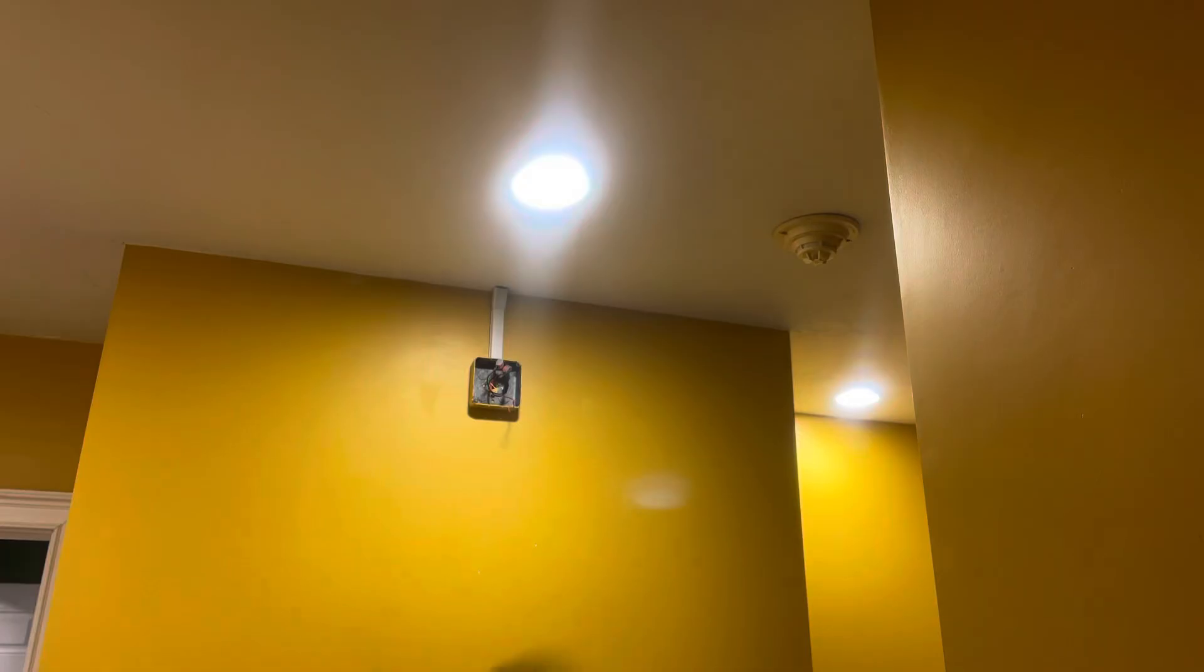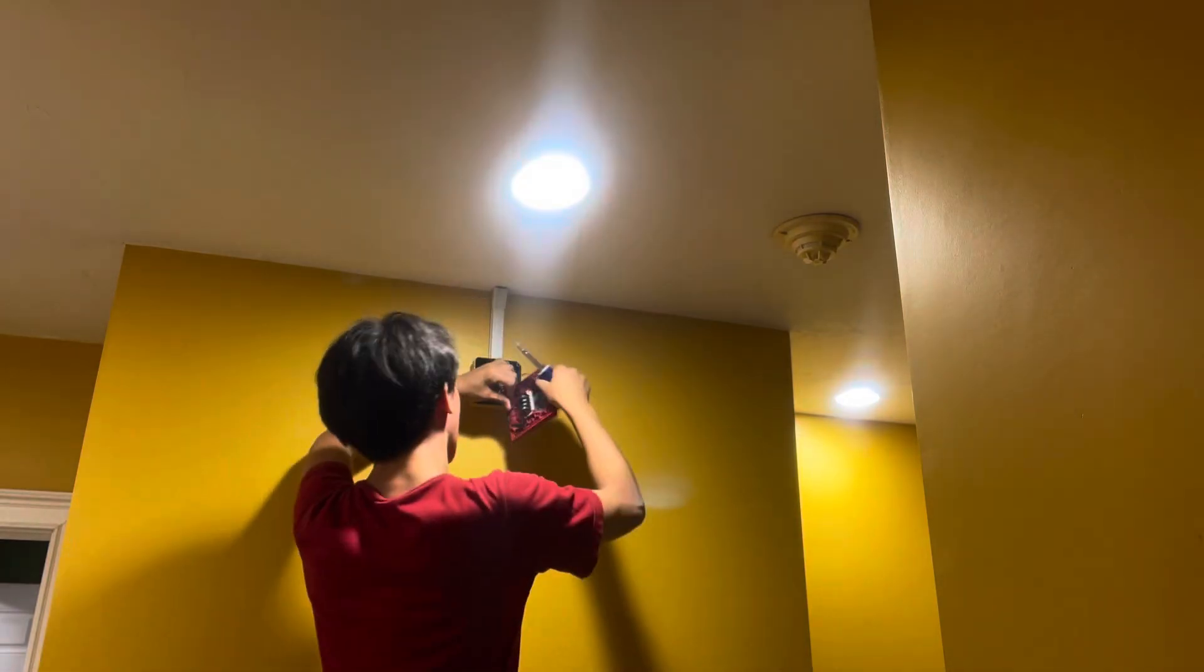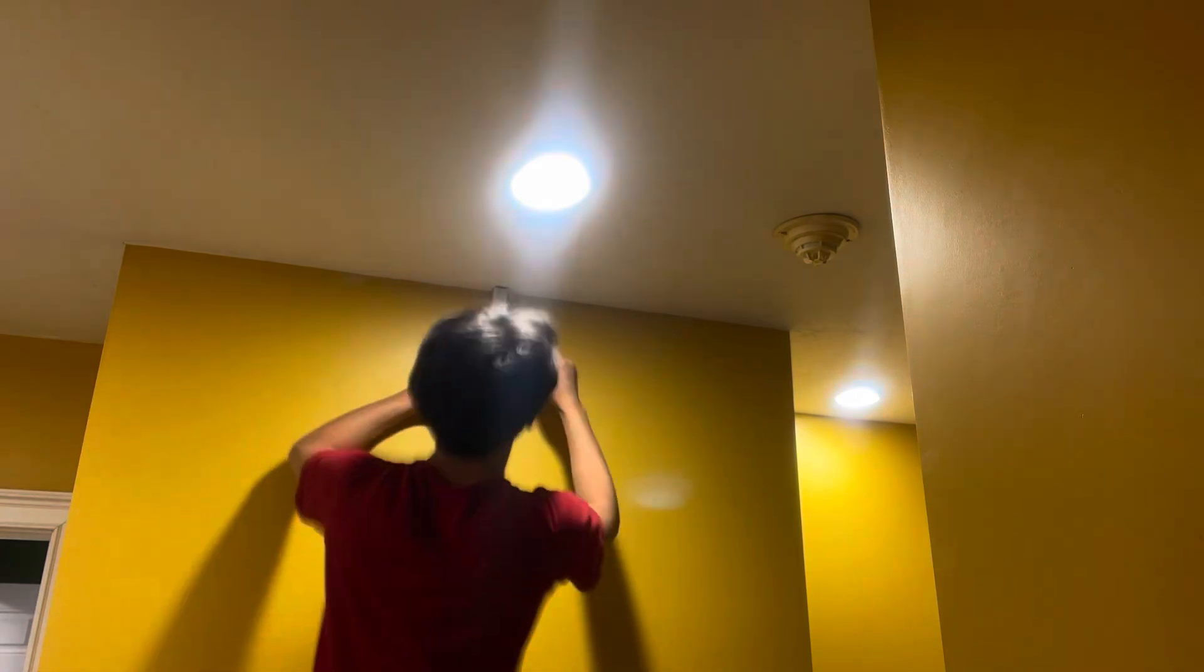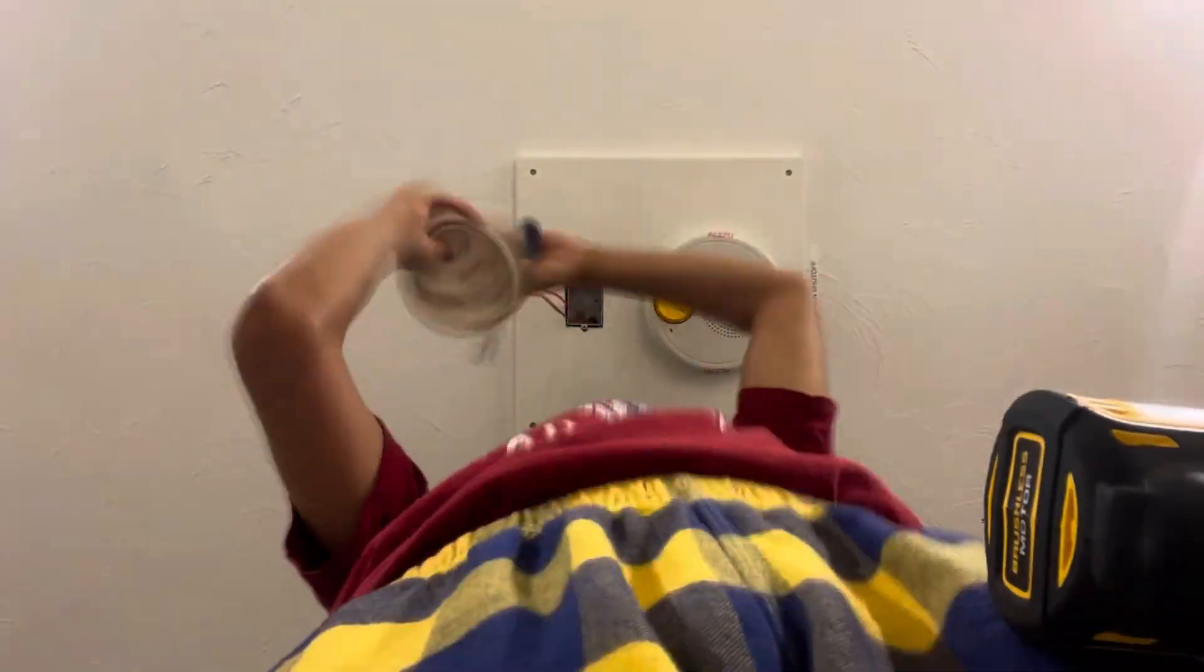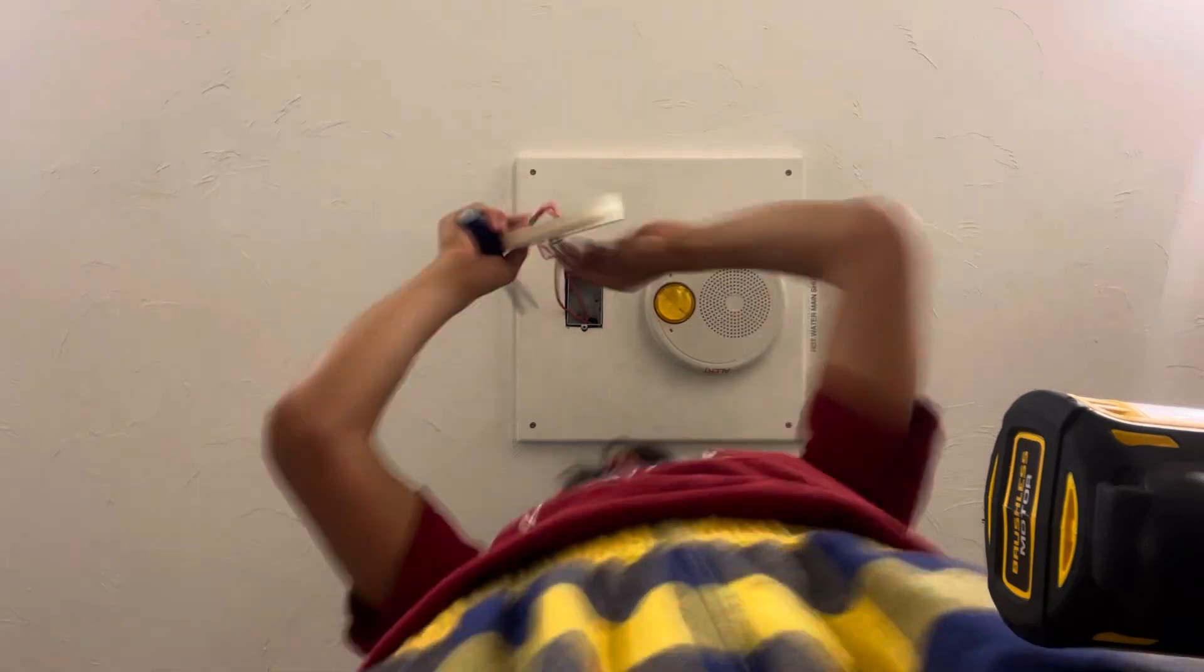So I could just plug the strobe straight into the terminals that the strobe of the TrueAlert plugged into, and I could use the same terminals on the speaker. The reason I did that is because the speaker on that unit is 70 volts, and generally 25-volt speakers just work way better with this system. I mean, both technically work. It's just that the 25-volt speakers require less power, so they're just a lot louder.